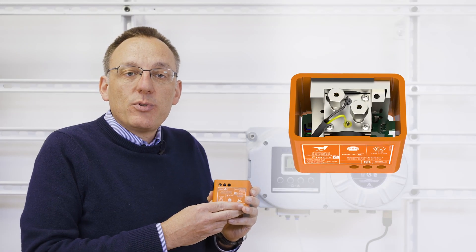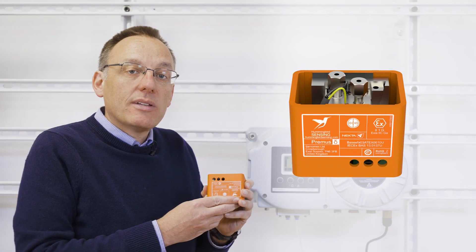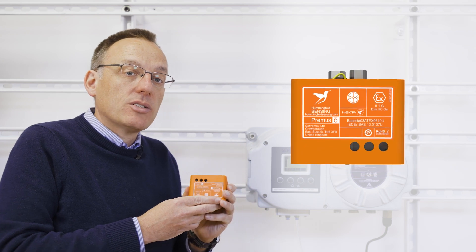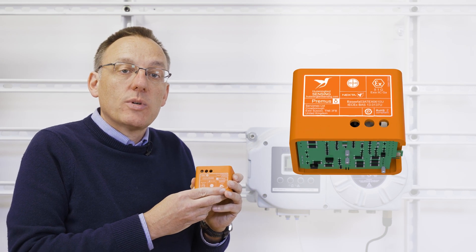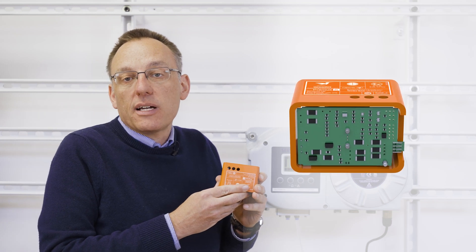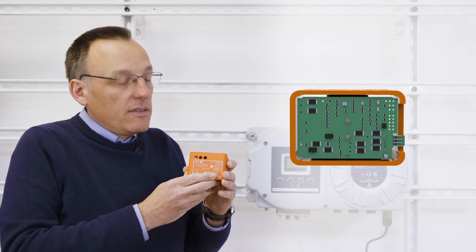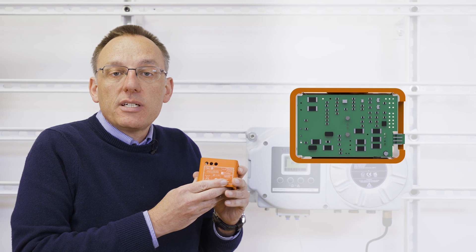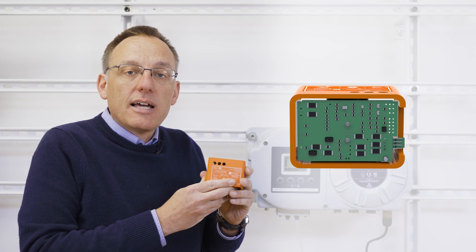It uses Servomex's proven Hummingbird 3601 digital paramagnetic sensing technology to measure oxygen up to 21% in samples that can also contain flammable gases.